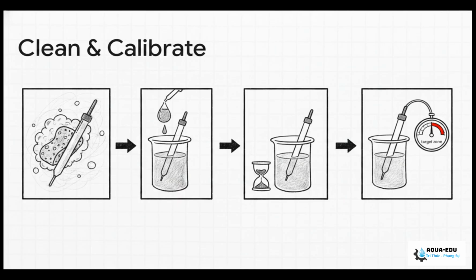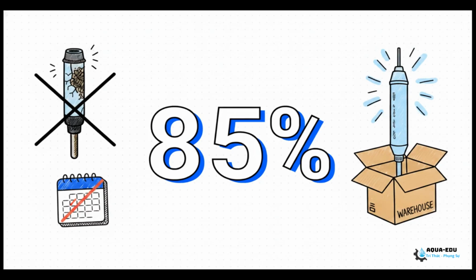We are aiming for a slope greater than 95% and a zero offset of less than plus or minus 20 millivolts. But what if you put in all that work? You scrub it, soak it, and it still fails. Well, that brings us to the magic number 85. If you've cleaned the probe perfectly, soaked it properly, and that slope is still sitting under 85%, it's completely dead. Or if the ceramic diaphragm is totally clogged up, or the probe is over 18 months old, just throw it out. Seriously, don't waste your shift fighting a dead probe. Go straight to the warehouse and install a brand new electrode.